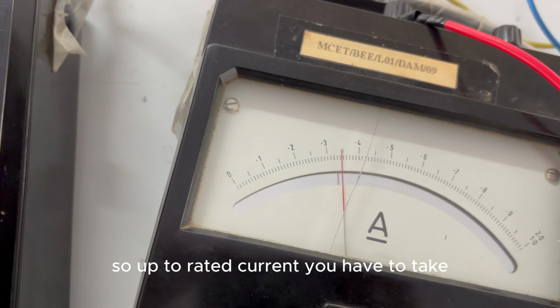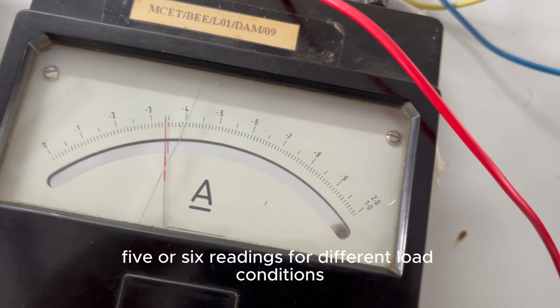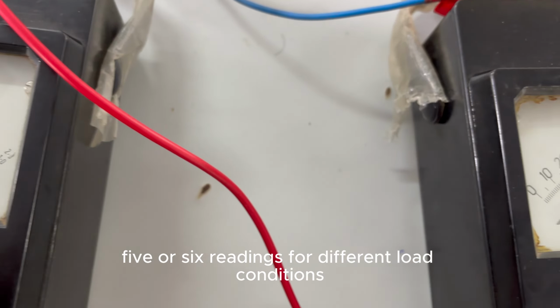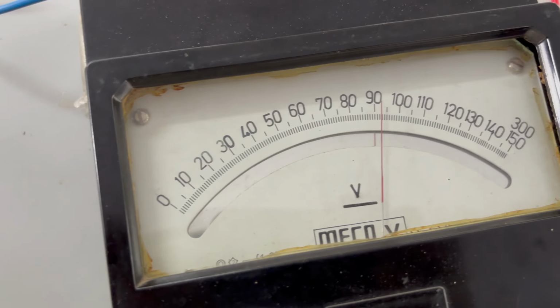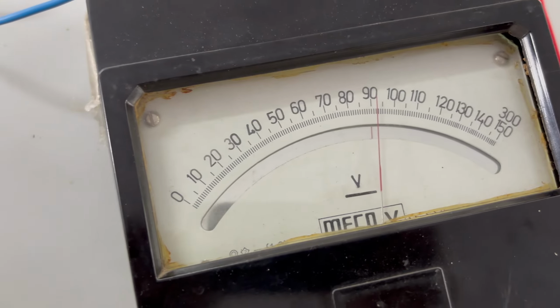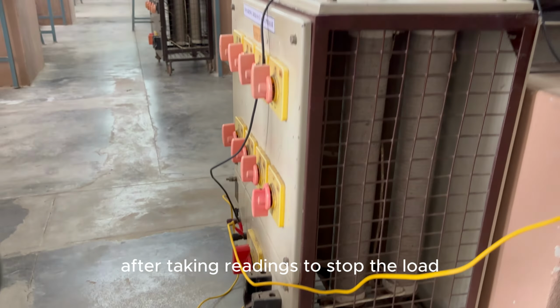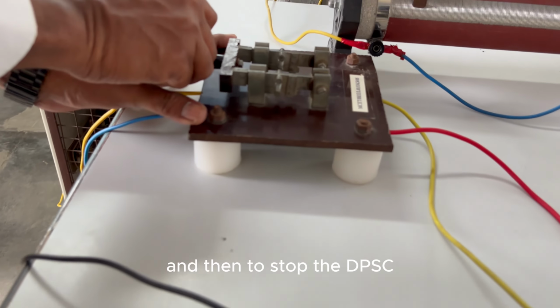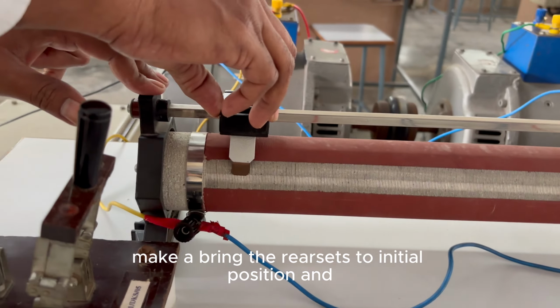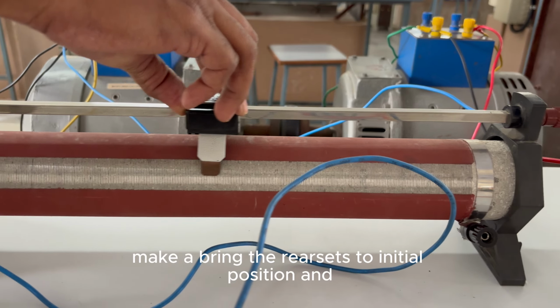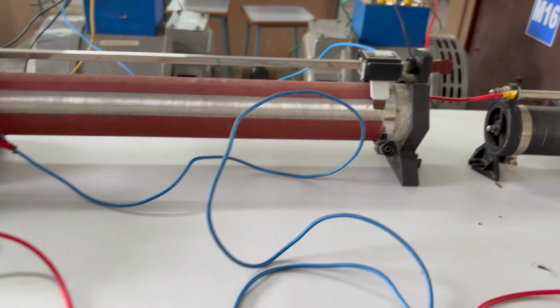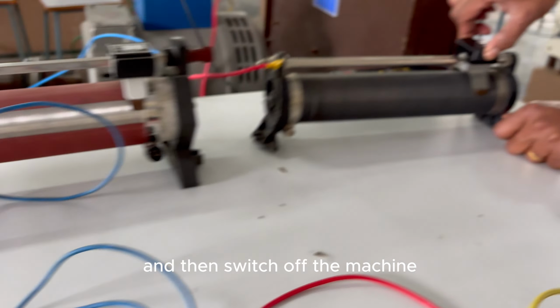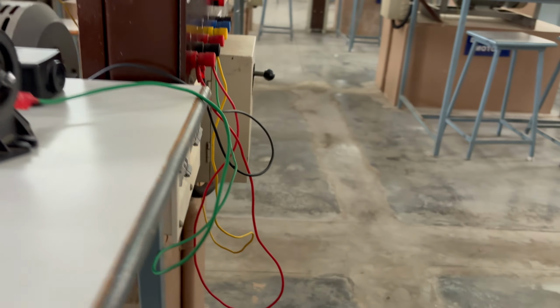Up to rated current, you have to take 5 or 6 readings for different load conditions: what is the voltage, the field current, the load current. After taking readings, switch off the loads and then switch off the DPSC. Bring the rheostats to the initial position and then switch off the machine.